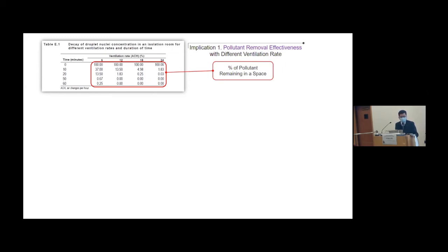The table shows that after 10 minutes, with an ACH of 6, around 60% of the pollutants are removed from the given space. As the ACH goes up, a much more significant reduction of pollutants is observed: from a removal of around 87% with an ACH of 12, up to a reduction of around 98% with an ACH of 24 within the 10-minute interval.